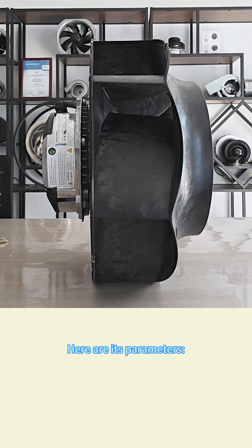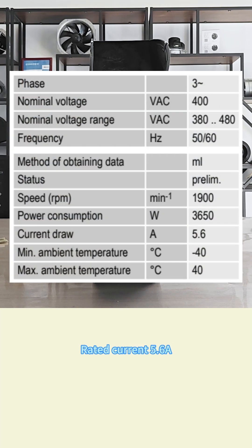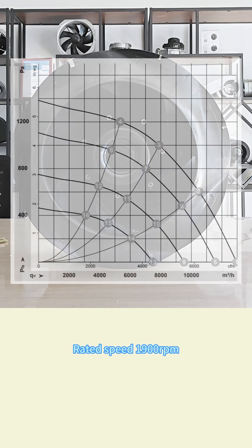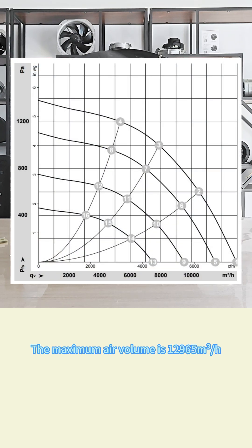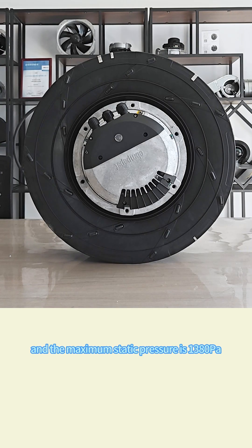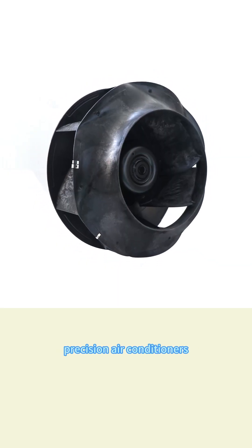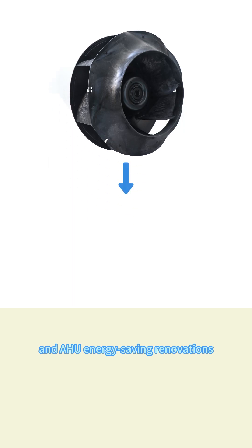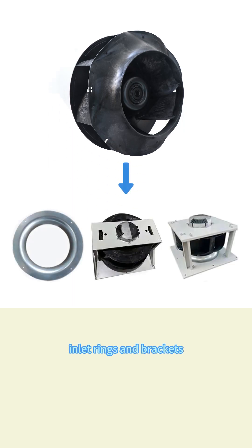Here are its parameters: rated voltage 400 volt, rated current 5.6 ampere, rated power 3650 watt, rated speed 1900 RPM. The maximum air volume is 12,965 cubic meter per hour, and the maximum static pressure is 1,380 Pa. This fan is commonly used in precision air conditioners, data centers, and AHU energy-saving renovations, and can be equipped with inlet rings and brackets.